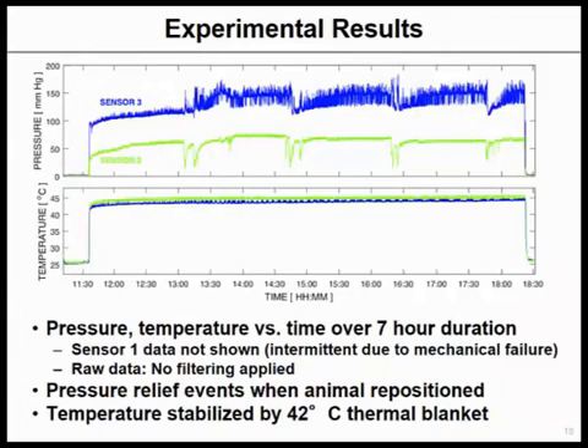So here's the experimental data. What we're looking at is on the vertical axis on the top plot, pressure in millimeters of mercury as a function of time. And the time goes from about 11:30 in the morning to about 6:30 at night. So during the first 20 minutes or so before the sensors are attached, that's kind of a convenient zero pressure control. Sensors are attached. Sensor 1 had some mechanical intermittent issues, so I'm not showing the data here. But when it was operating, it looked pretty much the same. You can see there's a lot more noise in sensor number 3 due to the nonlinearity. We chose to have the region of worst signal-to-noise ratio up at the maximum pressure where we're over the threshold and we don't really need to know the pressure that accurately.